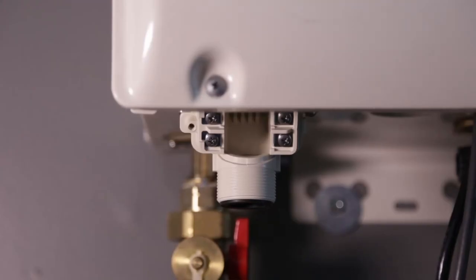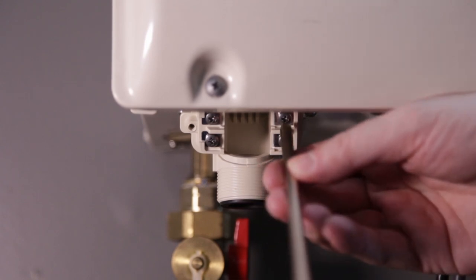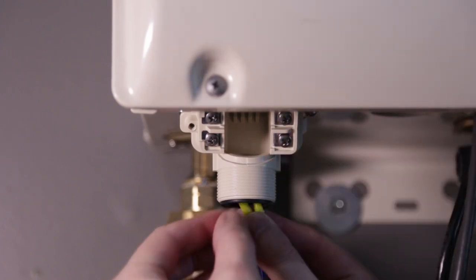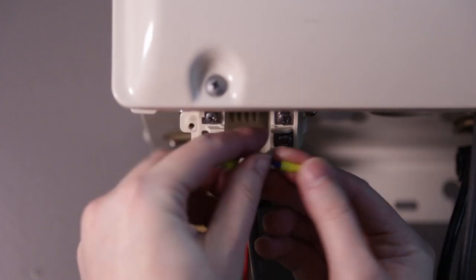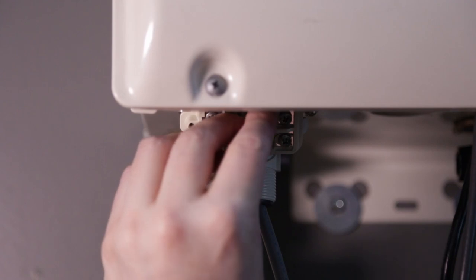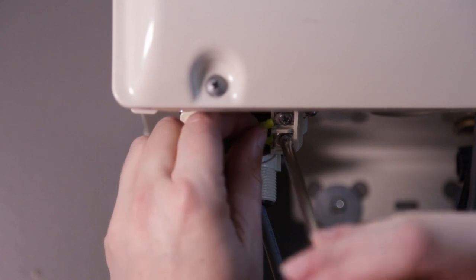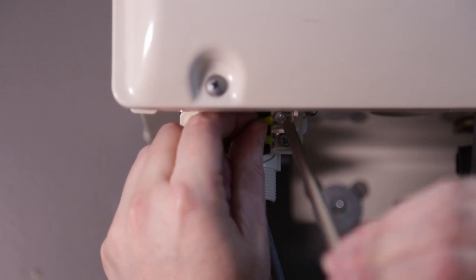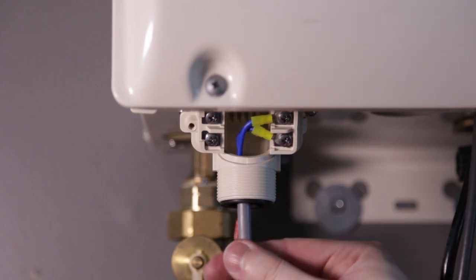Choose a pair of screws on either side and back them out just enough to slip the U-connector underneath. Connect one wire to each side. Fish the remote control wire through the rubber grommet and into the terminal box, then slip the U-shaped connectors underneath. Carefully hand tighten the screws back down — just enough to secure the terminals from slipping out. These connections are not polarity sensitive, so it doesn't matter which wire you connect to each terminal.